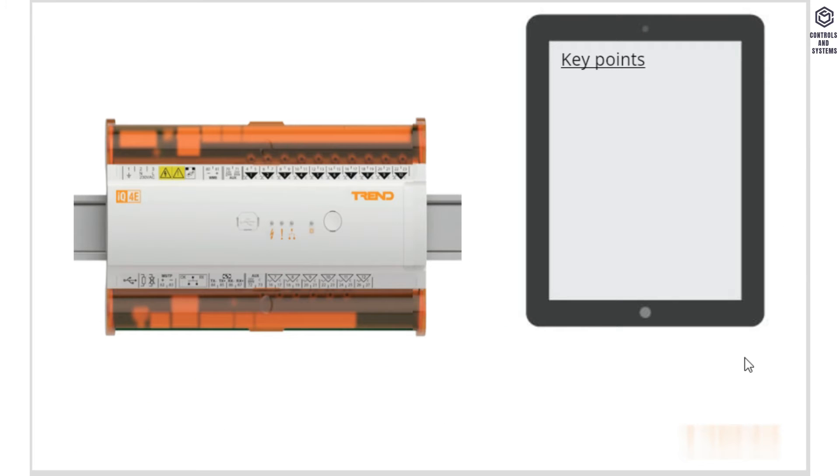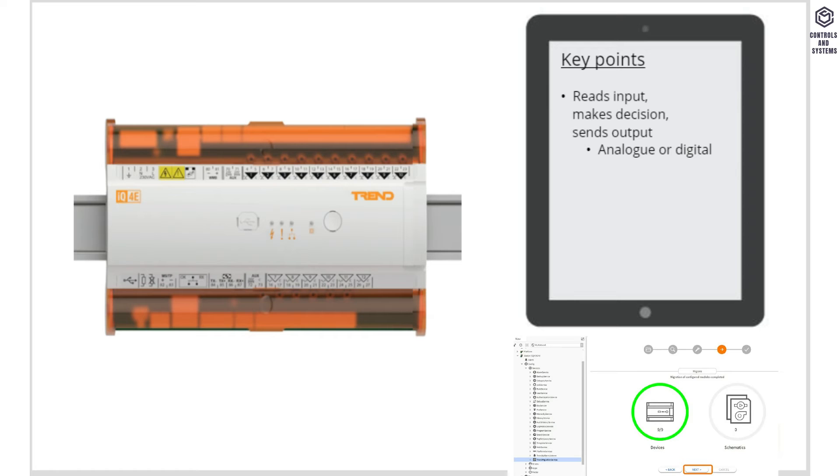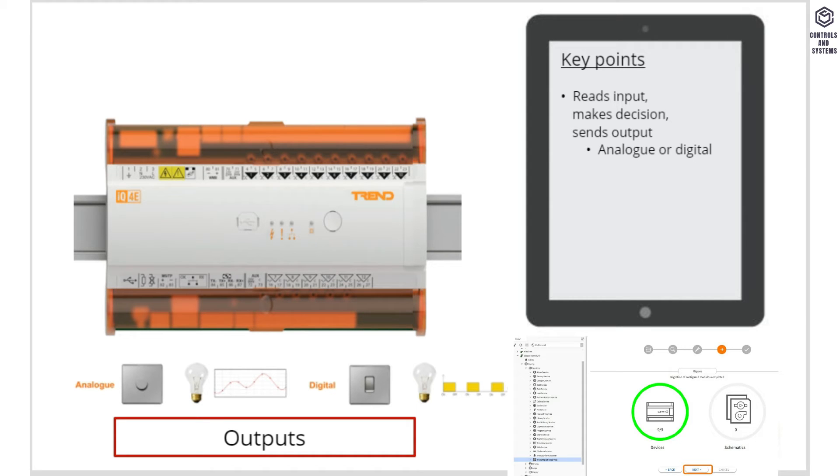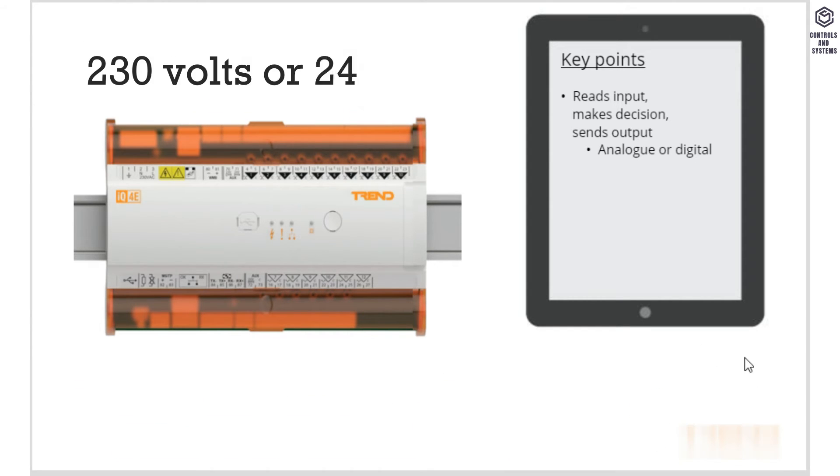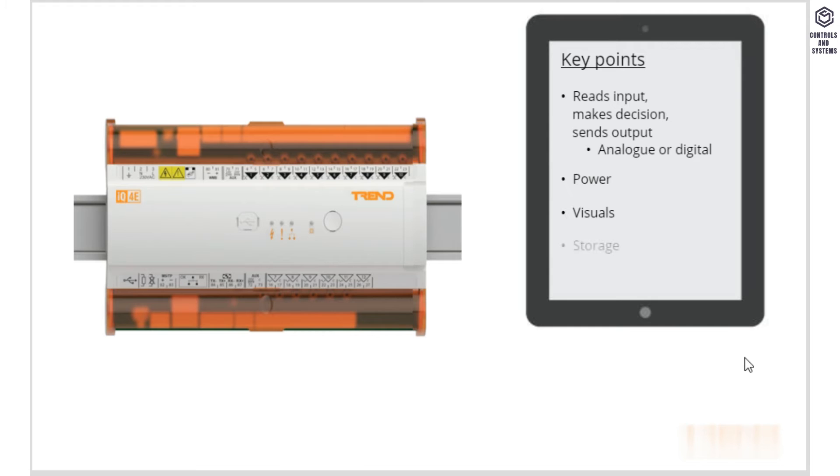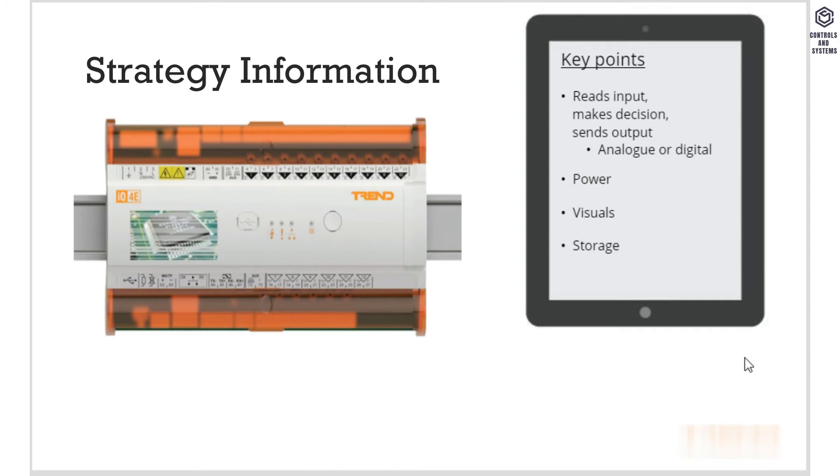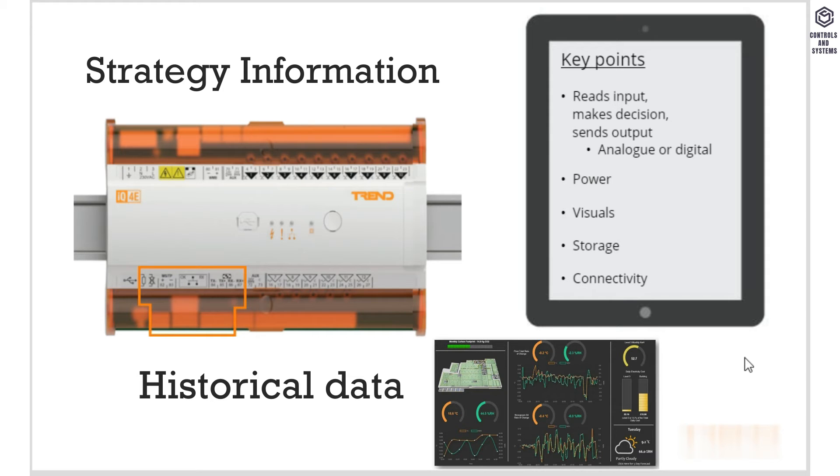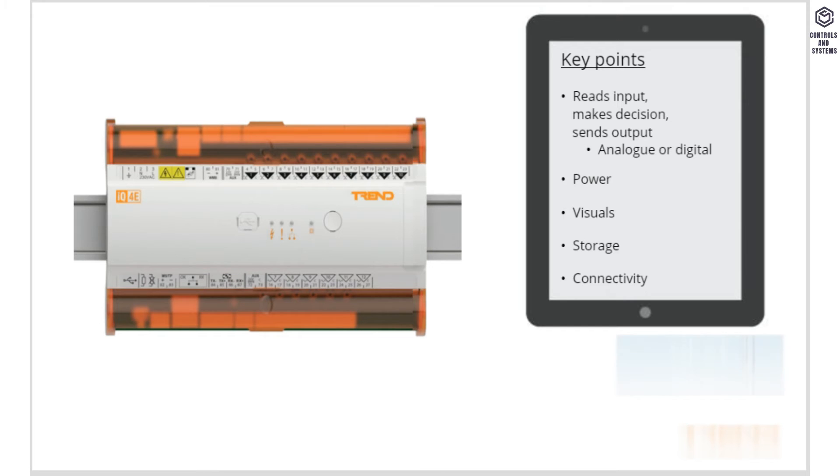The controllers take analog or digital device inputs and transfer the information into the strategy. The controller then decides what the outcome should be based on that information and sends output to a device. This could be turning equipment up or down (analog) as well as on or off (digital). It can be powered by a 230 volt or 24 volt connection and can also power other devices. The visual displays on the unit help troubleshoot your controller, for example, if the device is switched off and the controller thinks it's switched on. The controller also has built-in storage which is split into two parts: one part storing strategy information to help make decisions, and one part storing historical data that can be uploaded to the supervisor, for example, temperature room. Controllers can be connected to each other or a supervisor using a network. This can be either Ethernet, Trend Current Loop, or MSTP, depending on the controller type.